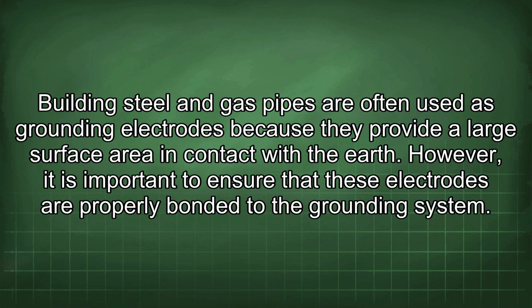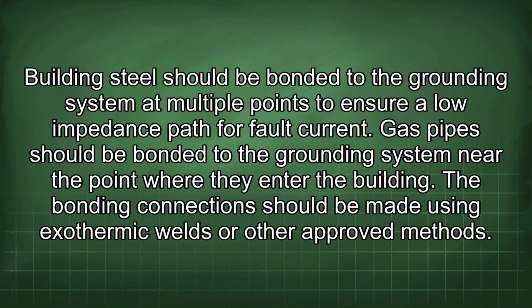Building steel and gas pipes are often used as grounding electrodes because they provide a large surface area in contact with the earth. However, it is important to ensure that these electrodes are properly bonded to the grounding system. Building steel should be bonded to the grounding system at multiple points to ensure a low impedance path for fault current. Gas pipes should be bonded to the grounding system near the point where they enter the building. The bonding connections should be made using exothermic welds or other approved methods.